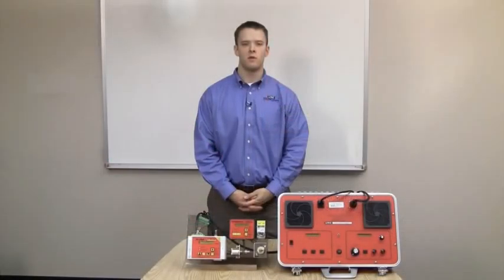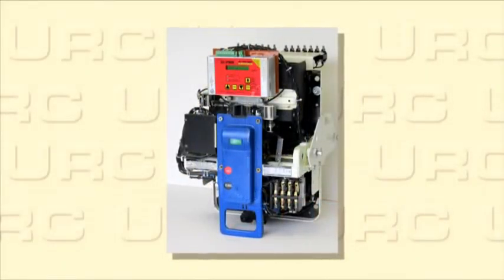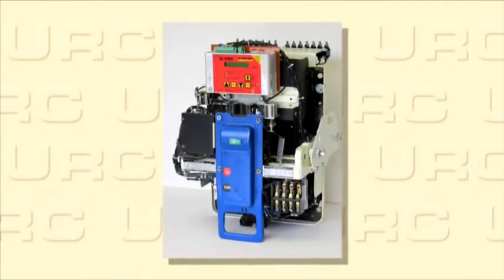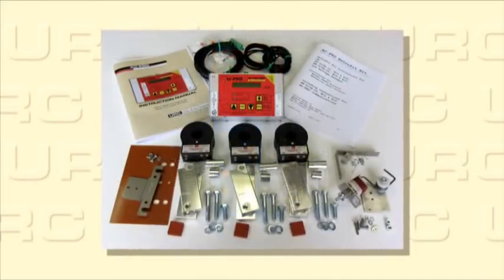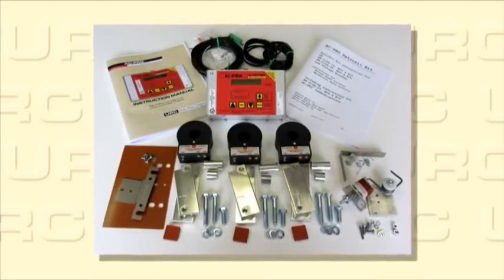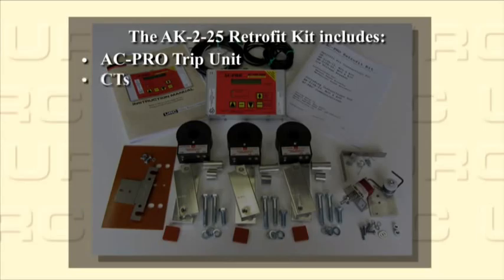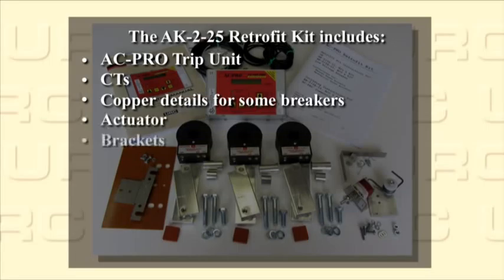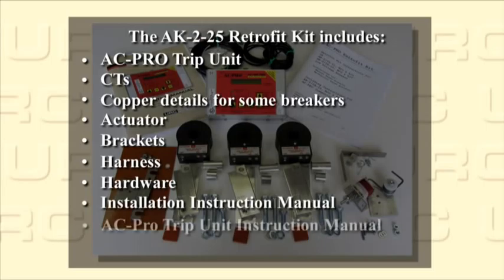The AC Pro trip unit is usually sold as part of a kit that includes everything you need to completely retrofit a breaker. This is the AK-2-25 breaker with the AC Pro retrofit kit installed. This is an AK-2-25 retrofit kit which includes an AC Pro trip unit, CTs, copper details which are needed for some breakers, actuator, brackets, harness, hardware, installation instruction manual, and an AC Pro trip unit instruction manual. We have over 1,000 kit designs and are always adding more. If you have a breaker that we do not have a kit design for, please let us know and we will work with you to design a kit for that breaker.